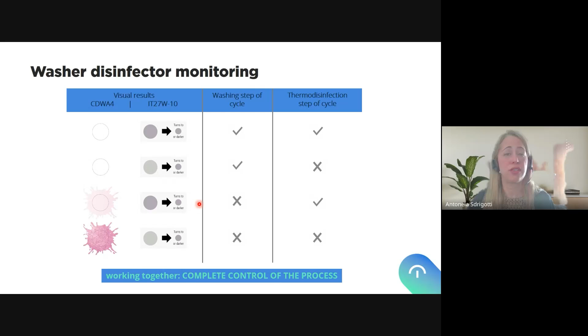Third row, here we can see we have a failure in the washing step, but the thermal disinfection step was right. And the last one is a total failure in both steps. So you can see that in the end, if we don't have separated monitoring for these two, we will be missing the thermal disinfection efficiency test.